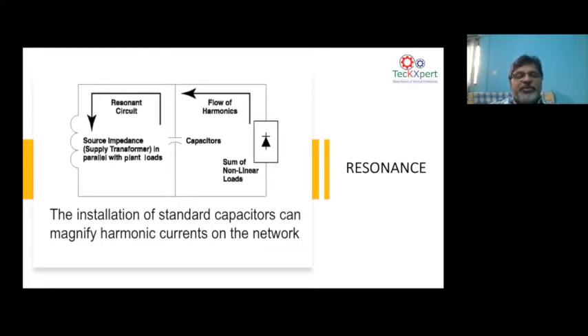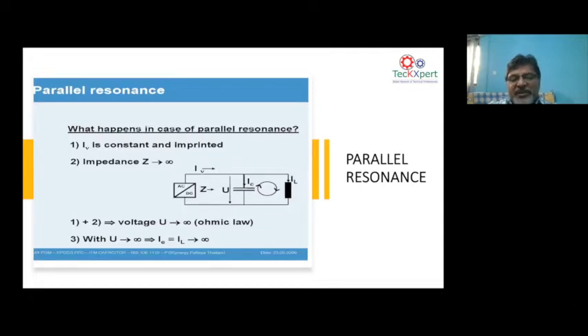And now the source impedance is your transformer or the rest of the network which belongs to BESCOM. Now here you can see the equivalent circuit shows the harmonic source on one side, the capacitor on the other side, and the rest of the impedance of the system, including the source impedance of BESCOM, as a parallel network. Go to the next one. So in this parallel network, you can see how parallel resonance is created when you have a harmonic producing load, as shown in this slide.